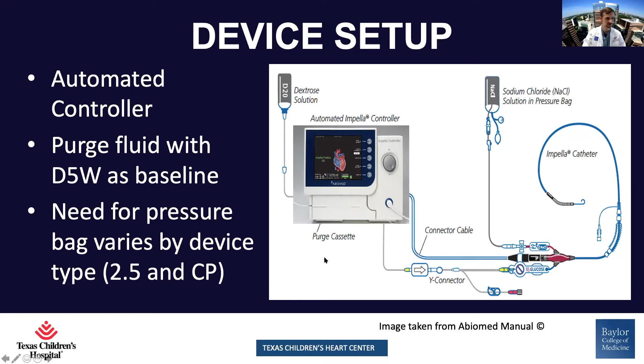I think one of the most attractive features of this device is the placement screen. The automated Impella controller displays a screen that allows us to extract various information. Most importantly, in the left lower corner, you can see the flow that the device currently provides. The flow is controlled through various P levels, and the P levels represent rotations per minute. So the higher the P level, the higher the rotations per minute, and the higher the expected output from the device. The P level starts at 0 and goes all the way up to 8. Some of the devices will contain what's called a boost mode or a P9 level, which enables the device to perform at its maximal setting.